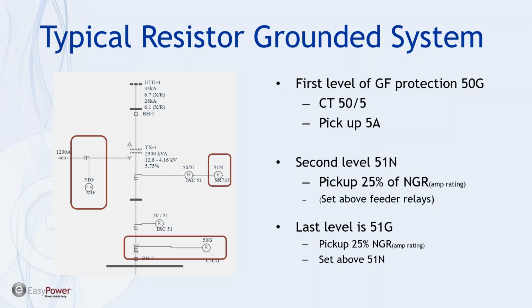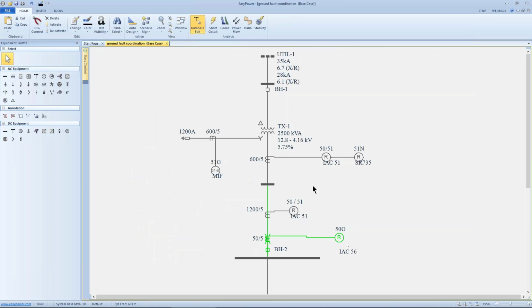And this again is rated, we want it to at least sense the current to start to pick up at 25% of the rating, and we want it to be coordinated with the elements below it. So let's jump into EasyPower and see how this works.